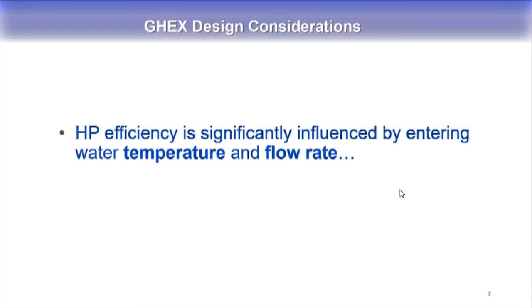For management, the big thing that killed this heat pump market in the 80s was lack of attention to detail, and the fact that we had a bunch of heat pumps pretty much set in a very narrow range, 55 degrees up to about 77, 85 degrees. Got above that, they started blowing compressors. Got below that, they just went down on low head.